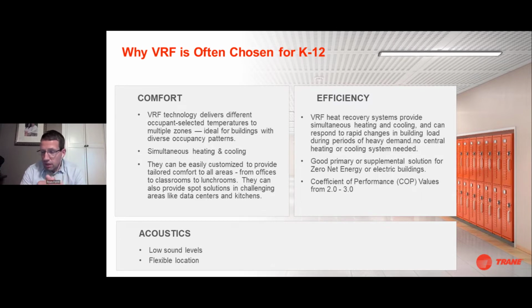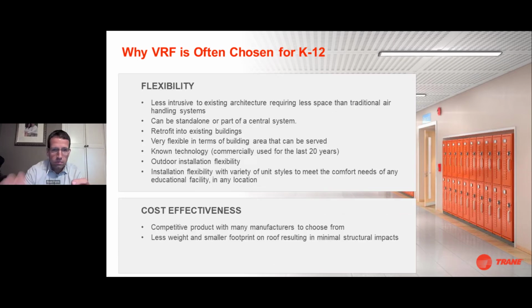Low sound levels. These outdoor condensing units consist of a propeller fan and either one or multiple compressors inside an insulated cabinet. And also location flexibility. If you're close to a property line, you can shift these systems away from the building, almost anywhere on the roof, or away from these property lines or these sound sensitive areas. Flexibility. It's less intrusive to building architecture, and it takes up less space than traditional air handling systems.